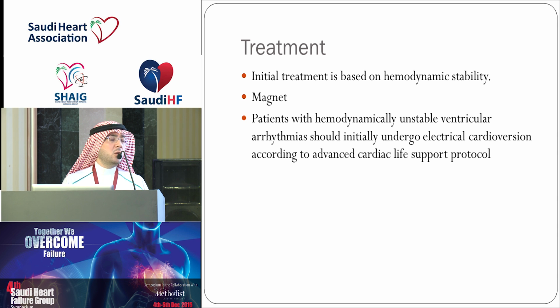What you need to do is just put the magnet on the ICD. If you put a magnet on a pacemaker, it will pace continuously and become asynchronous. But what happens if you put the magnet on an ICD? It will prevent detection — basically, you deactivate shocks and deactivate ATPs. The device will not deliver therapies.